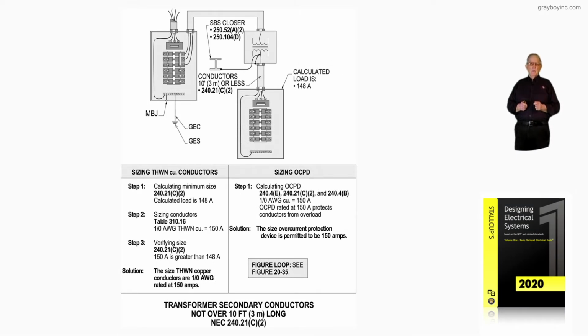Now, this illustration deals with the industrial installation of secondary conductors, not over 25 foot long, in accordance with NEC 240.21(C)(3). Many times questions come to me: how do you size those primary conductors? Well, we would go to Table 450.3(B) if that primary voltage was 1,000 volts or less. We would take the primary full load current of that transformer times 125% and size our conductors and our overcurrent device. Now, if you wanted illustrations of this, then look at our figure loop.